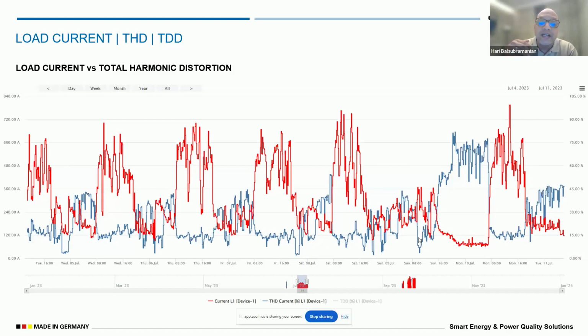If you see, when the current goes high, THD goes low. When the current goes low, the THD goes higher and higher, especially at the end, in this kind of area where the THD is slightly higher. So which means, can we take total harmonic distortion as a parameter to ascertain whether we have more harmonics or not? No, it is not possible.